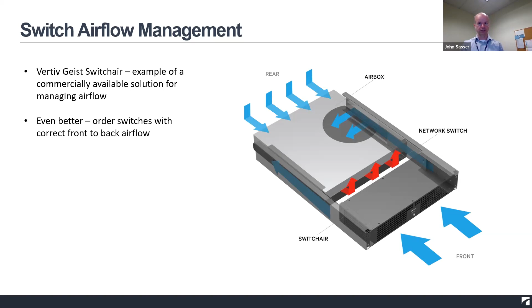Typically the racks you see in a data center are not fully loaded, so you need blanking plates between the servers. Very often network switch manufacturers aren't overly concerned with proper airflow, so they design equipment that pulls air in from the back and discharges to the front or side, which makes managing airflow more challenging. There are solutions for that, and we've worked with our customers to help implement them.